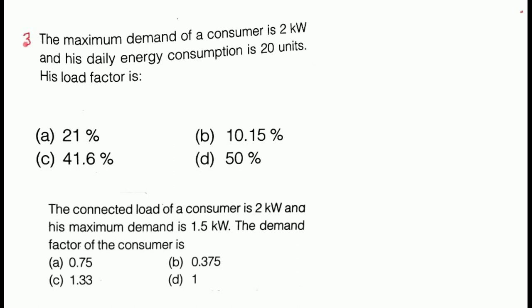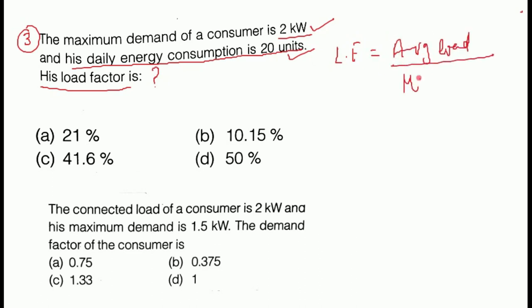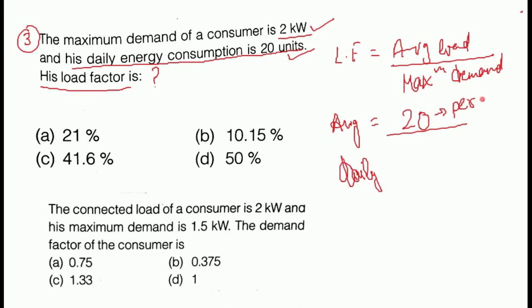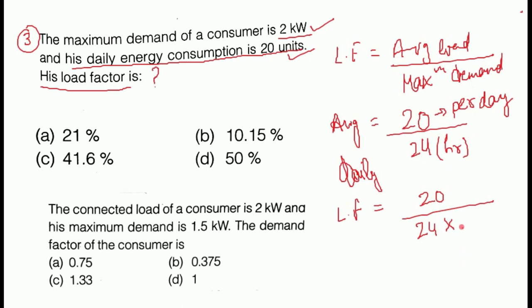Next is question number 3. The maximum demand of a consumer is 2 kW and his daily energy consumption is 20 units. His load factor will be what? Load factor is equal to average load divided by maximum demand. Average load equals total energy consumed — 20 units — divided by total time in hours. The daily energy consumption is 20 units, meaning 24 hours. So load factor = 20 / (24 × 2) = 0.4166, which as a percentage is 41.6%.